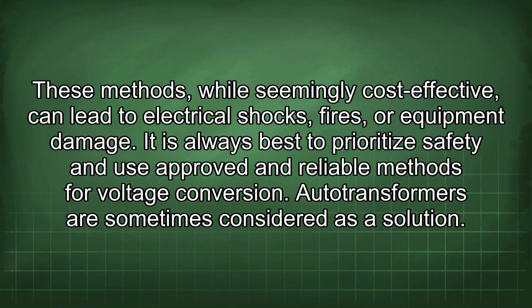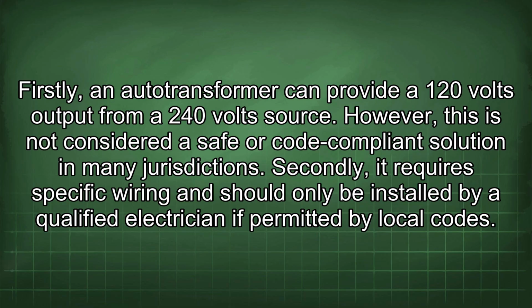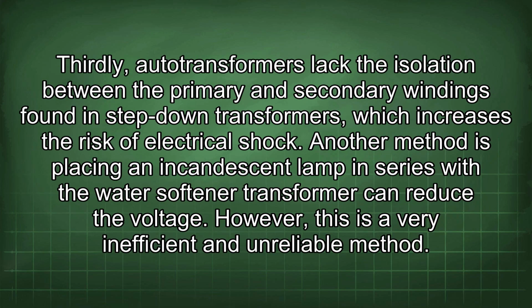Auto transformers are sometimes considered as a solution. Firstly, an auto transformer can provide a 120 volts output from a 240 volt source. However, this is not considered a safe or code-compliant solution in many jurisdictions. Secondly, it requires specific wiring and should only be installed by a qualified electrician if permitted by local codes. Thirdly, auto transformers lack the isolation between the primary and secondary windings found in step-down transformers, which increases the risk of electrical shock.